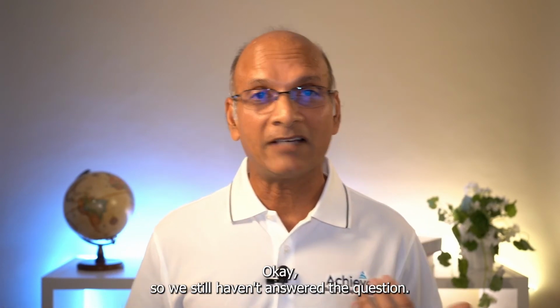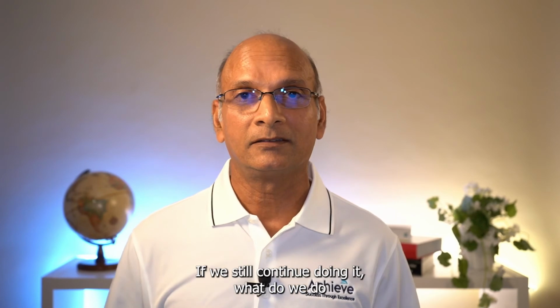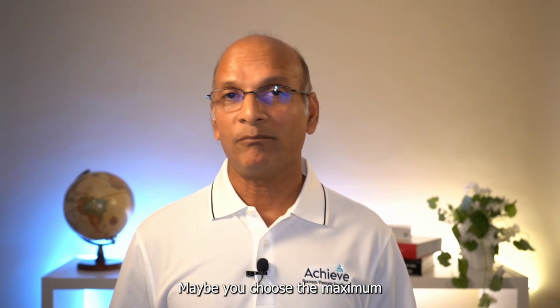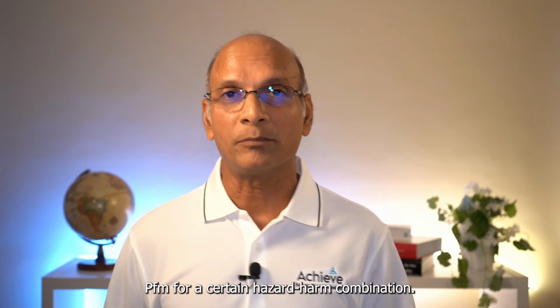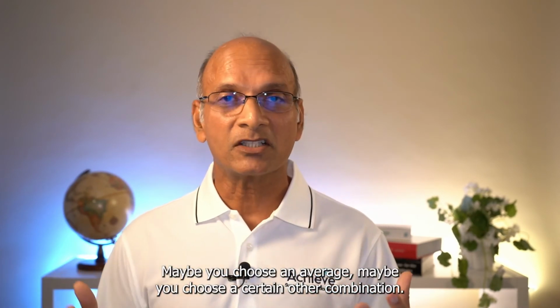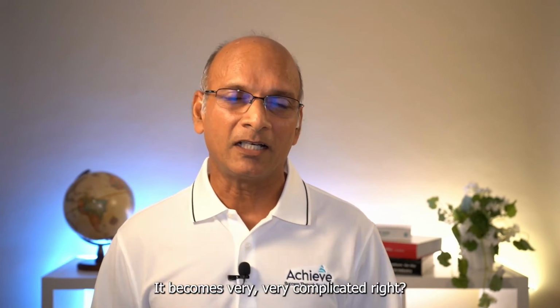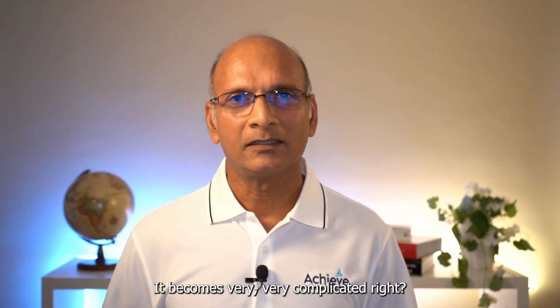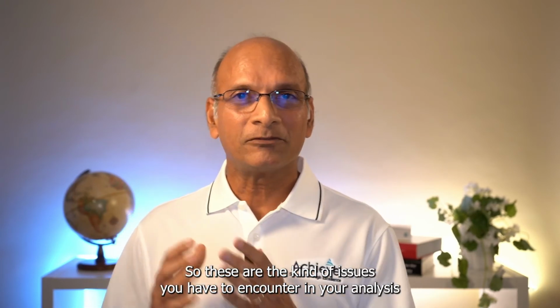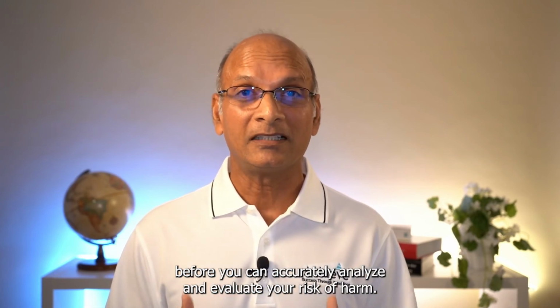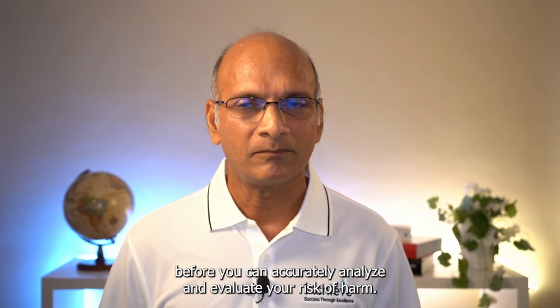Okay, so we still haven't answered the question, what do we do if we still do it? If we still continue doing it, what do we do? Then you have to make some decisions. What is most relevant? Maybe you choose the maximum PFM for a certain hazard harm combination. Maybe you choose an average. Maybe you choose a certain other combination. But whatever you do, you have to make some assumptions and write it down. It becomes very, very complicated, right? So these are the kind of issues you have to encounter in your analysis before you can accurately analyze and evaluate your risk of harm.